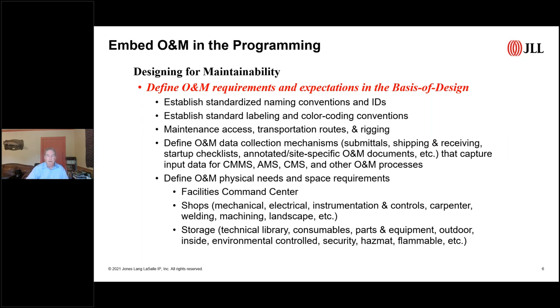Maintenance access and transportation routes, especially for your largest and most difficult equipment to access, must be planned for in the design. For example, a building had a sixth-floor chiller plant with large 880-ton chillers. Getting those chillers in and out was difficult even during construction, and once the building is closed up, it's even harder. So we had to build in a knockout in a wall so cranes could rig the chillers in and out. You need to plan for this so you're not stuck unable to replace equipment. Define the O&M data collection mechanism.